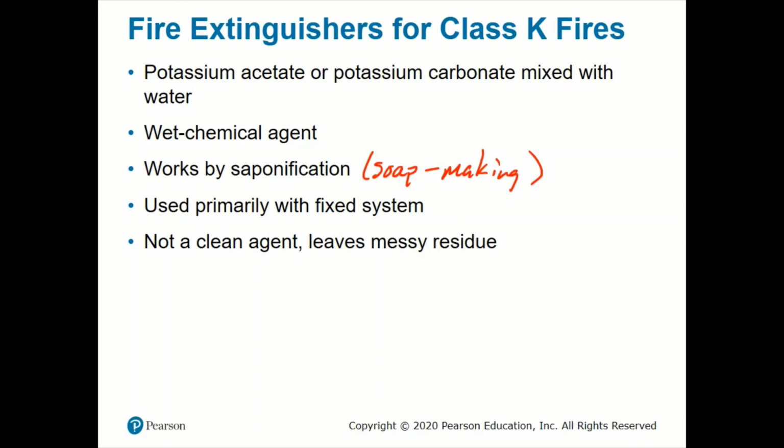Anyone knows that if you take water to hot oil, it just bursts up in flames, because the water forms steam, and the steam causes more oil to evaporate, and it just goes up in a big flame. So initially you see that, but very quickly those chemical agents go to work, and the fire's out in less than 30 seconds, usually. Now these are done within a fixed system.